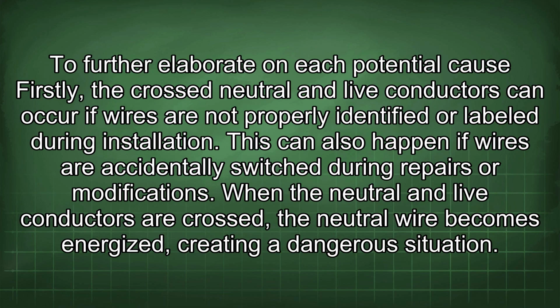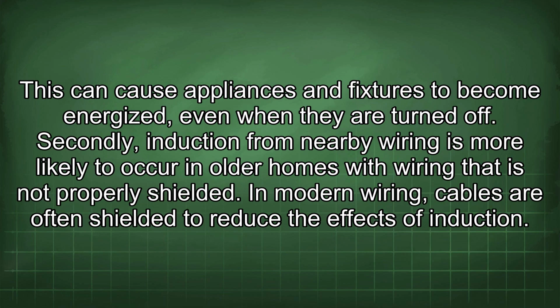To further elaborate on each potential cause, firstly, the crossed neutral and live conductors can occur if wires are not properly identified or labeled during installation. This can also happen if wires are accidentally switched during repairs or modifications. When the neutral and live conductors are crossed, the neutral wire becomes energized, creating a dangerous situation. This can cause appliances and fixtures to become energized even when they are turned off.